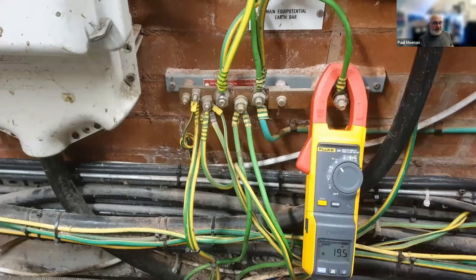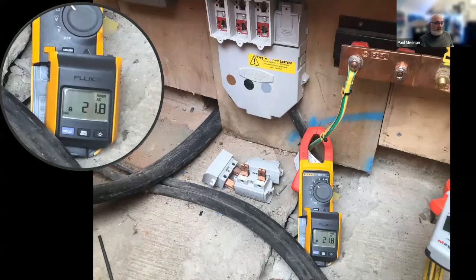This is a picture that I took. There's 20 amps on an earthing conductor. So that's the fixed electrical installation to the power supply. You don't really want 20 amps on an earthing system, considering that in England, I was taught that it's a benign conductor with 0 volts. Generally, they're millivolts behind this, but we'll get into that phenomenon in a second.